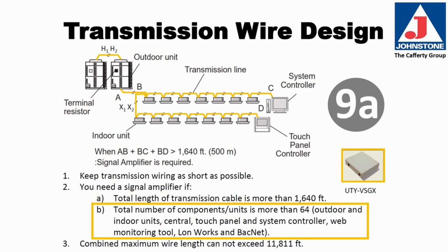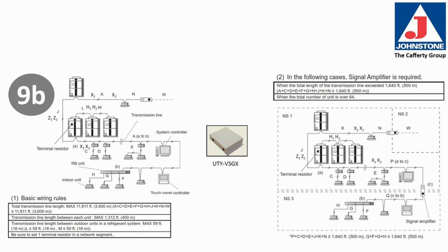The total number of components or units is more than 64. That's outdoor units, indoor units, central controller, touch panel and system controllers, web monitoring tool, LonWorks, and BACnet. Combined maximum wire length for all the communication cannot exceed 11,811 feet. Basic communication wiring rules. Total transmission wire length maximum: 11,811 feet. That is a total of all of the components together.